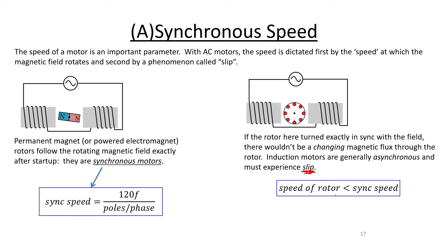You need slip. In other words, the speed of the rotor, that squirrel cage, must be less than the synchronous speed—the speed of the rotation of the magnetic field around the stator. In a synchronous motor, the speed of the rotor and the synchronous speed are equal, but in an induction motor, the speed of the rotor is always less than the synchronous speed.